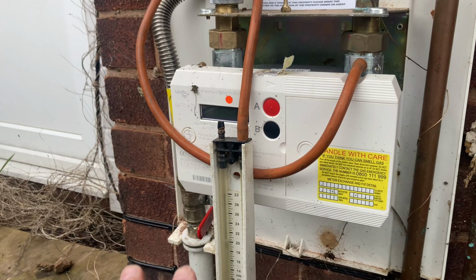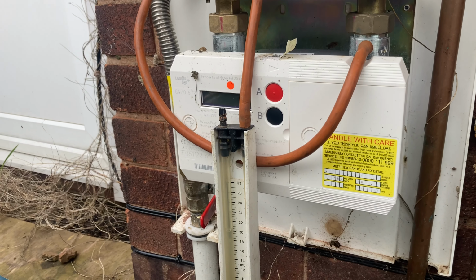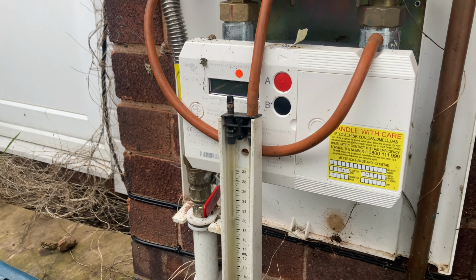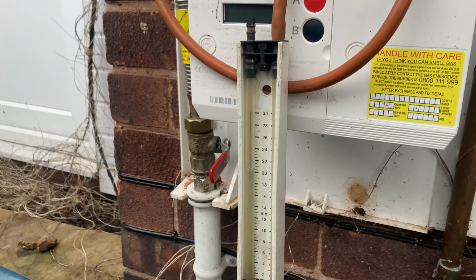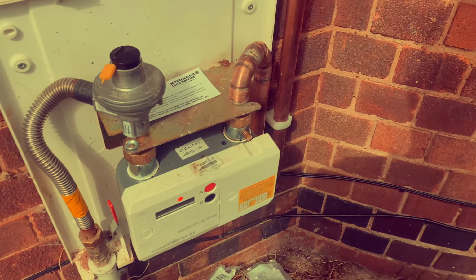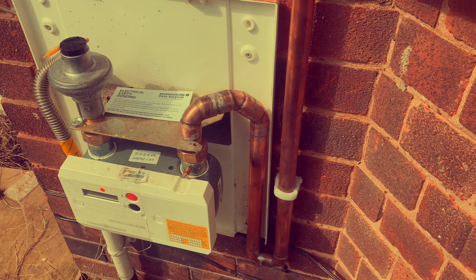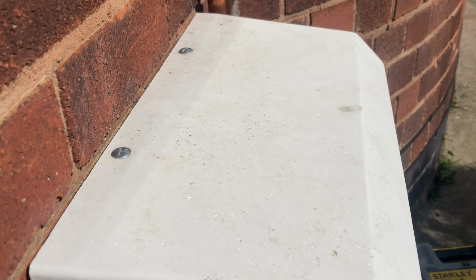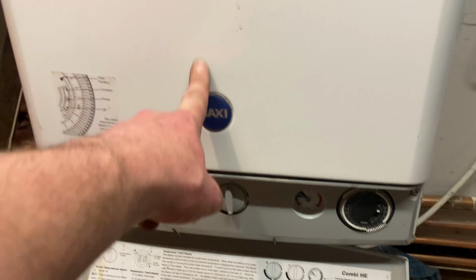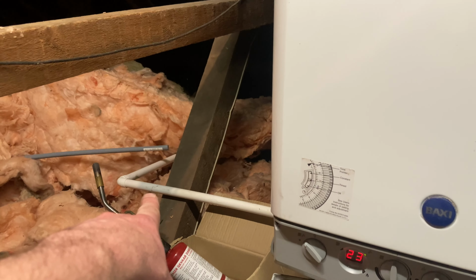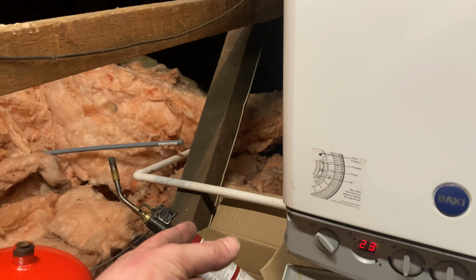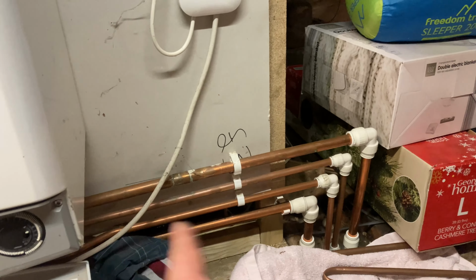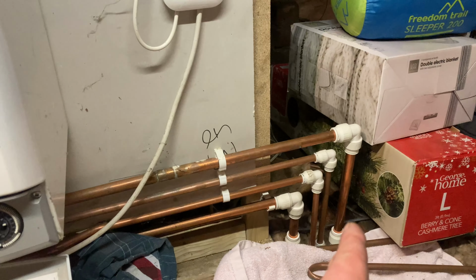So before I begin, I'm doing a tightness test. I want to check that the current pipework, existing pipework, has no leaks and it's not dropping. So I've increased the pipework diameter to 28 mil, so the boiler can function efficiently. Expansion vessel's gone. Condensation pipe needs insulating because this is an unheated area, so it's classed as external. Should be at least 1 metre to 2 metres before any plastic or speed fit. Might put some extra supports in.